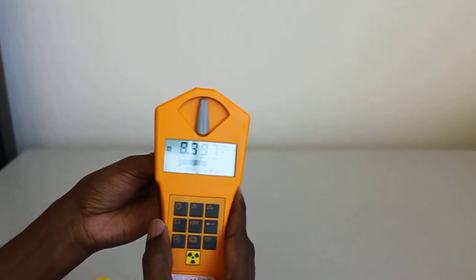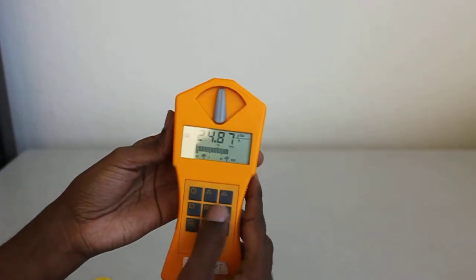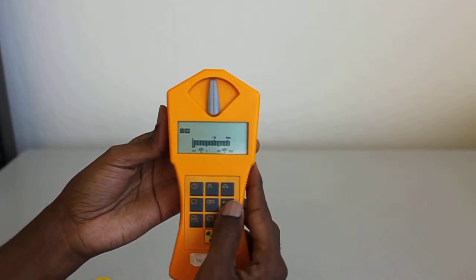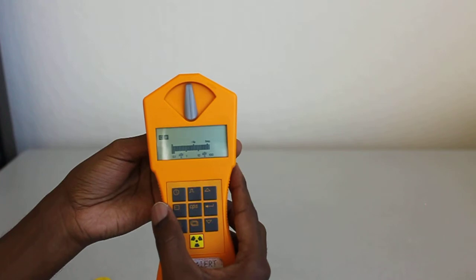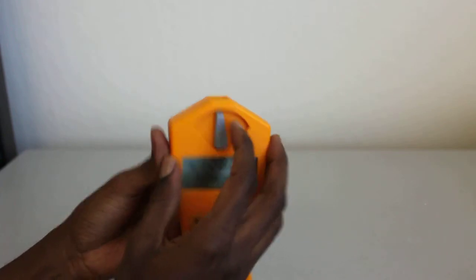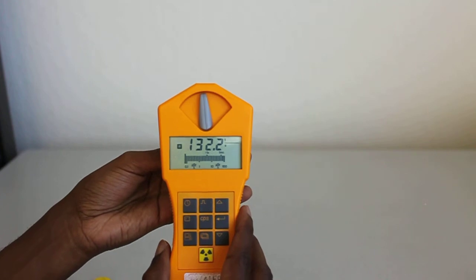Let's hold this over here. We're seeing in microsieverts per hour, but I want counts per second, so let's change that reading. Its sensor is right over here. You can actually see the top of the tube over there. I'm just going to hold it across here, across the back, like that.